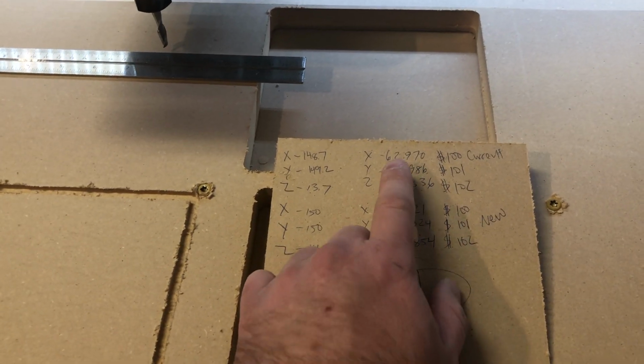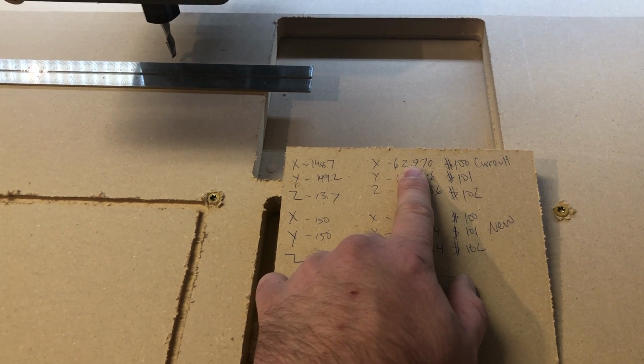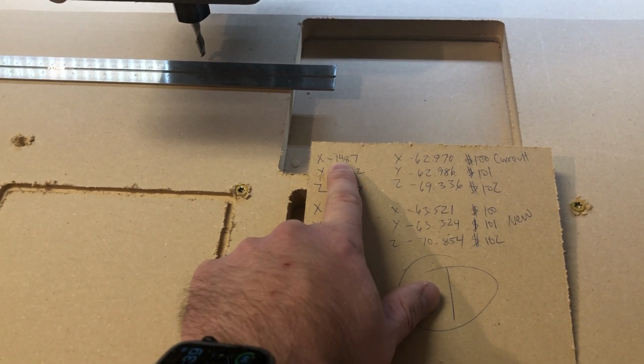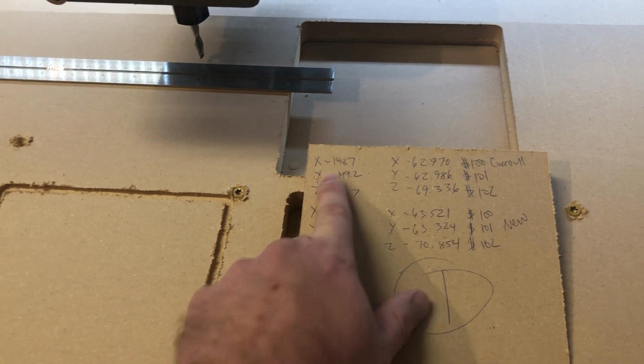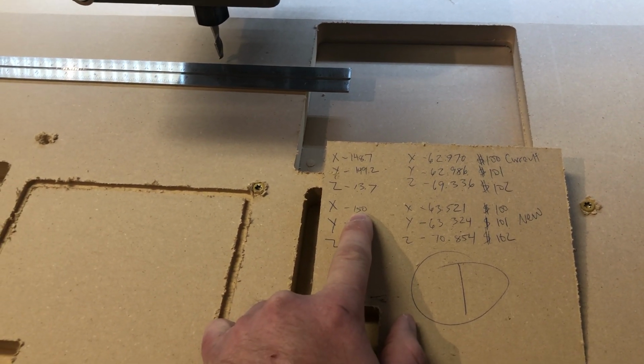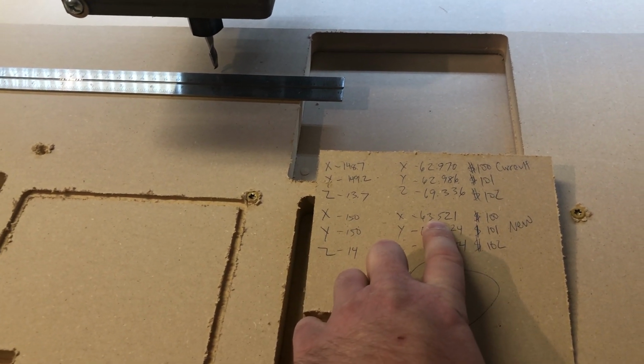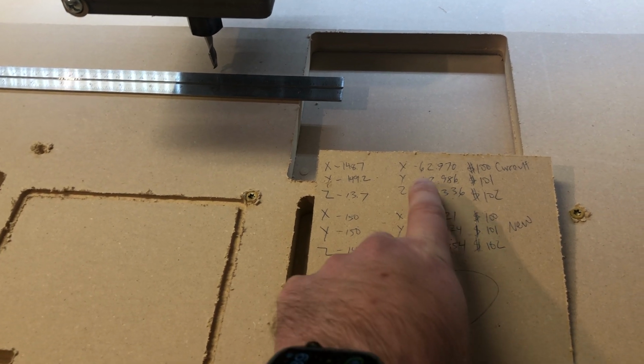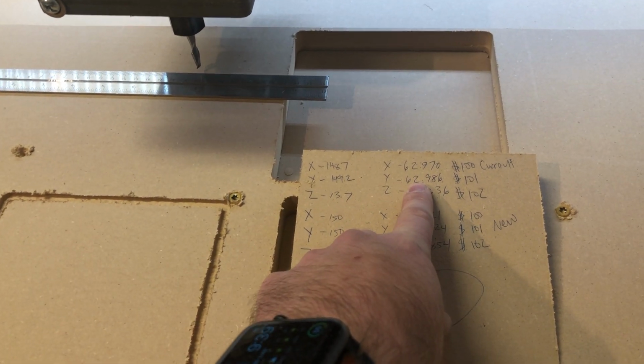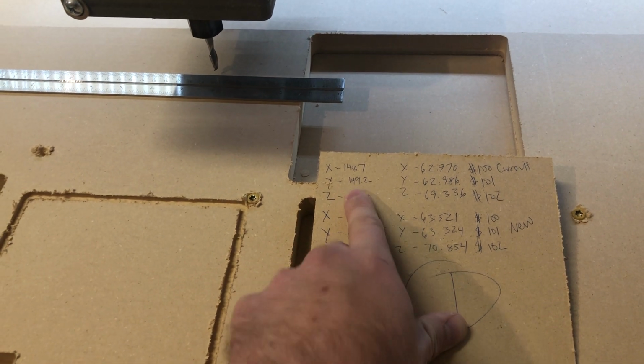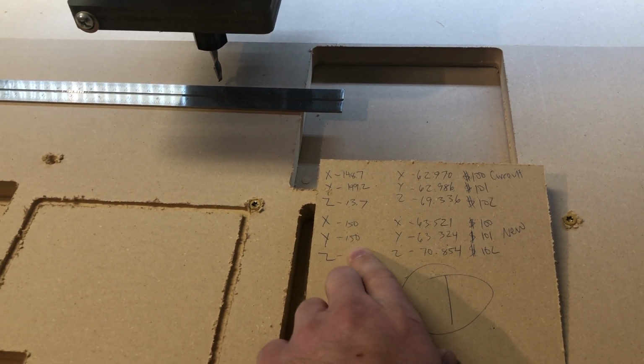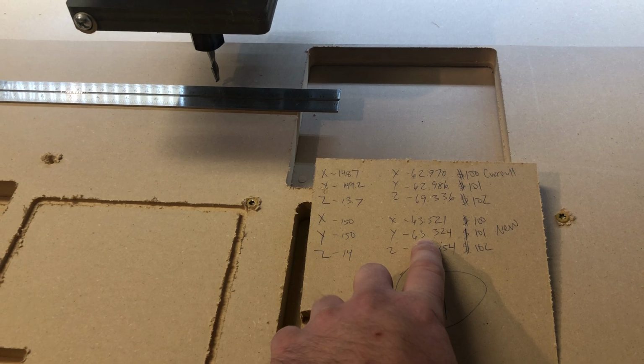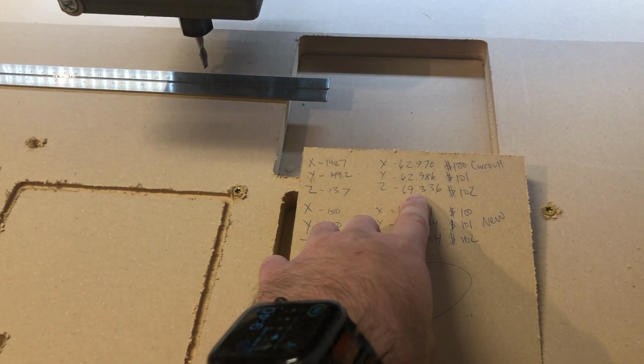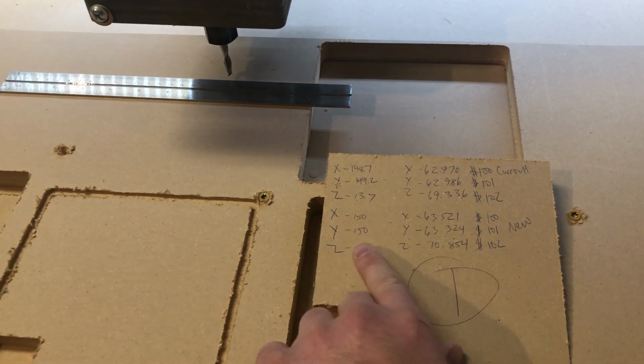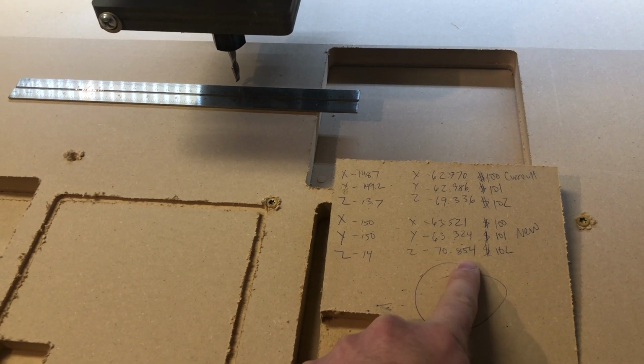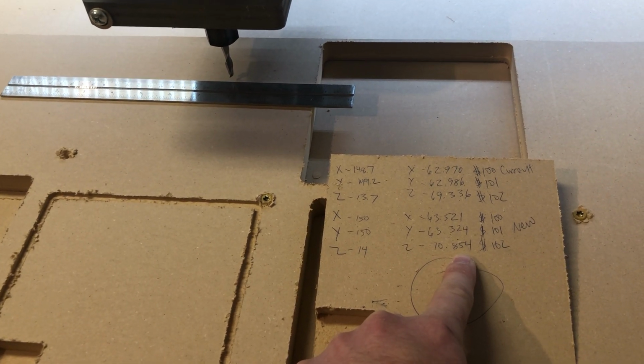So to come up with the new 100, 101 settings, you have to divide 62.970 by 148.7, and multiply that by 150—that yields 63.521. You do the same thing for Y: 62.986 divided by 149.2, times 150, gives 63.324. And 69.336 divided by 13.7, multiplied by 14, gives 70.854.